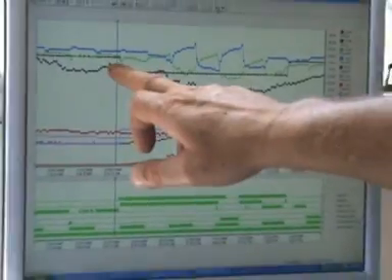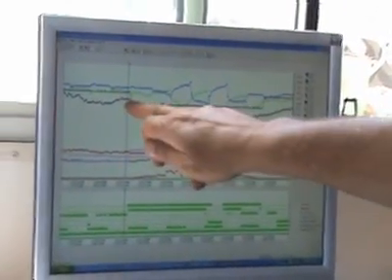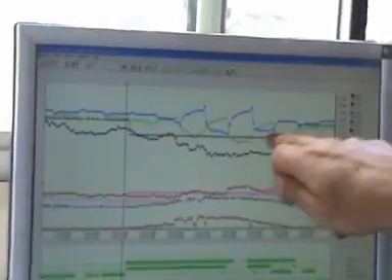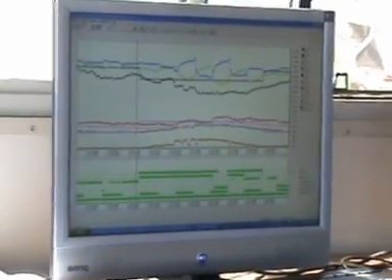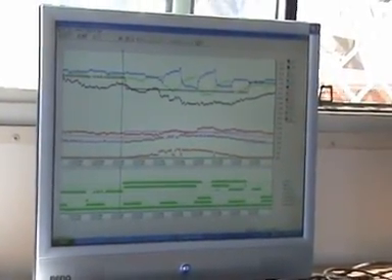So we've got weather, ambient temperatures, kiln temperatures forward and reverse. We've got the humidity levels inside the kiln. There's a control line. We've set it for 65%, and the system is operating to maintain that. You can see the vents here have been operating and opening to reduce humidity, and at times a water spray has been coming on automatically to boost humidity, depending on the condition of the kiln. Very important, we control the conditions inside the kiln very, very minutely. So we're able to see this from here on site, use it for process optimization, but most importantly, we're able to use this as a system of monitoring from afar.